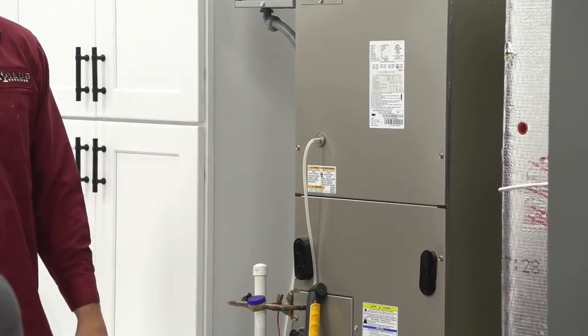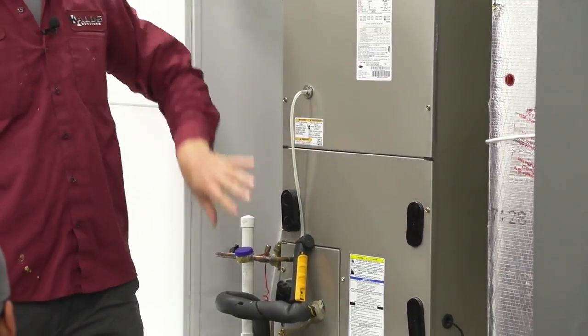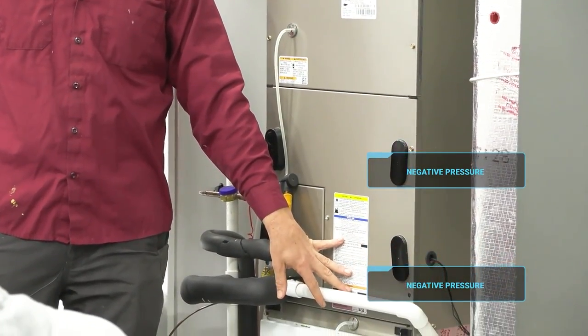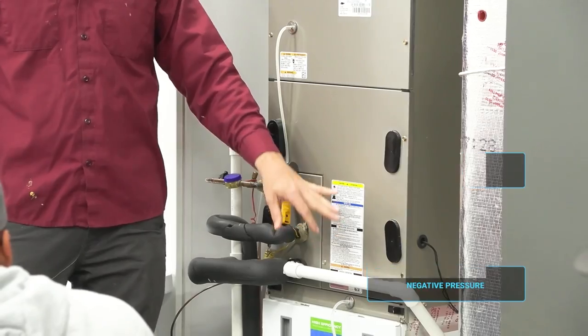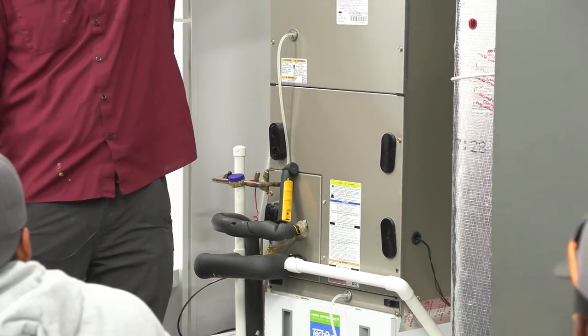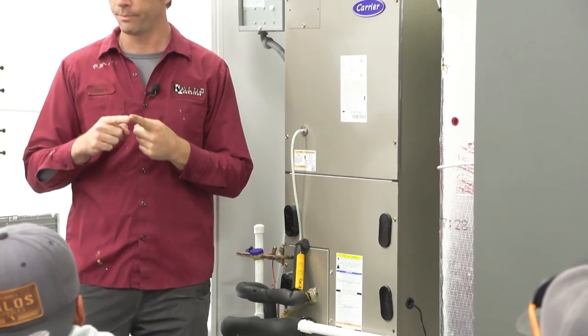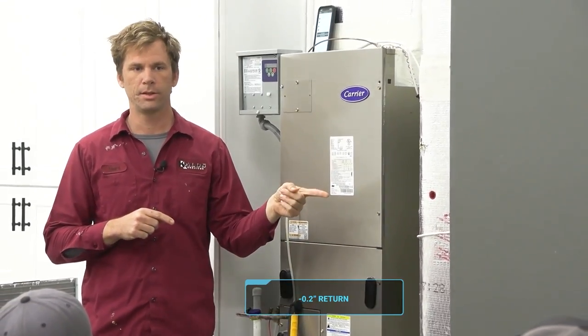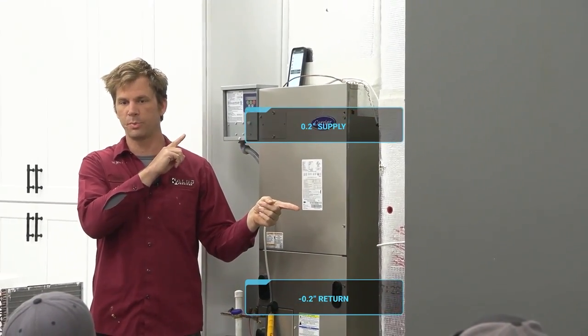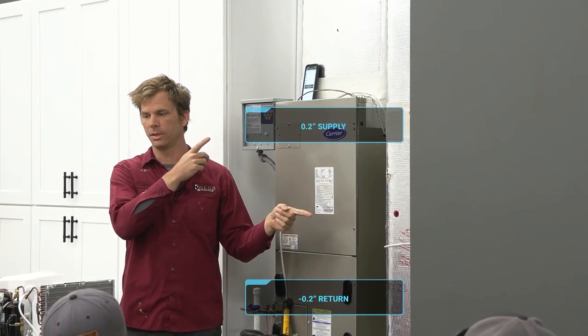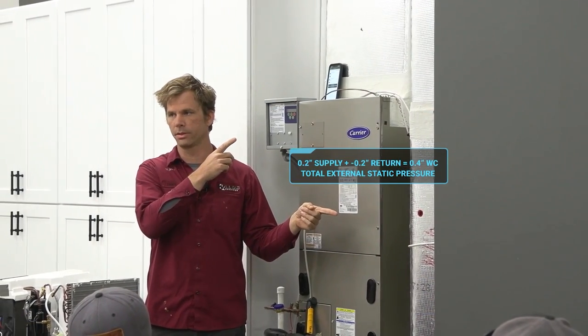The unusual thing here is that both these areas are negative pressure. Typically when we are doing our reading, we have our positive and negative, and we take those two numbers and add them. If we have -0.2 plus +0.2, what's our total external static? 0.4. It's 0.4, not zero.